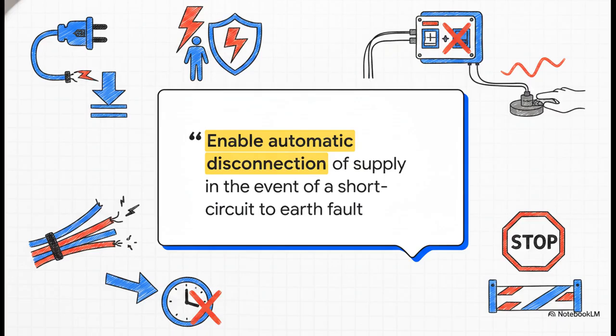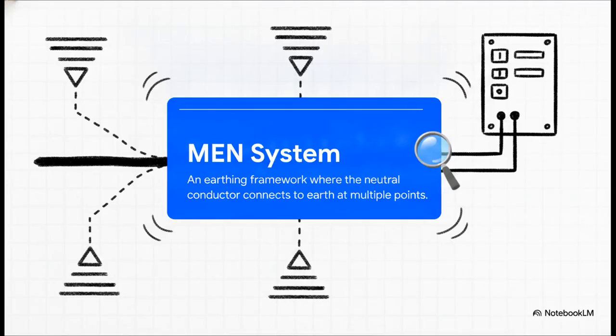But how exactly does a static bundle of wires do that automatically? Okay, let's dive into this. Meet the MEN system, the multiple earth neutral. This is the absolute bedrock of electrical installations in our region. Instead of just crossing our fingers and relying on one single path to the ground, the MEN system connects the neutral conductor to the earth at multiple points across the network. And crucially, it does this right at your main switchboard. It basically creates this incredibly robust, highly reliable framework that is perfectly designed to catch and redirect any of those rogue currents.